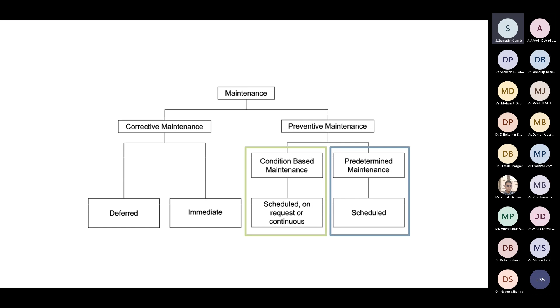This goes more in detail, but I won't go too much into it. Typically for a steam turbine, we have a fixed maintenance period, like 25,000 operating hours. You have to open the machines, inspect everything. If it's okay, you box it up; certain parts you have to replace. This is the traditional inspection method, or the current inspection method.